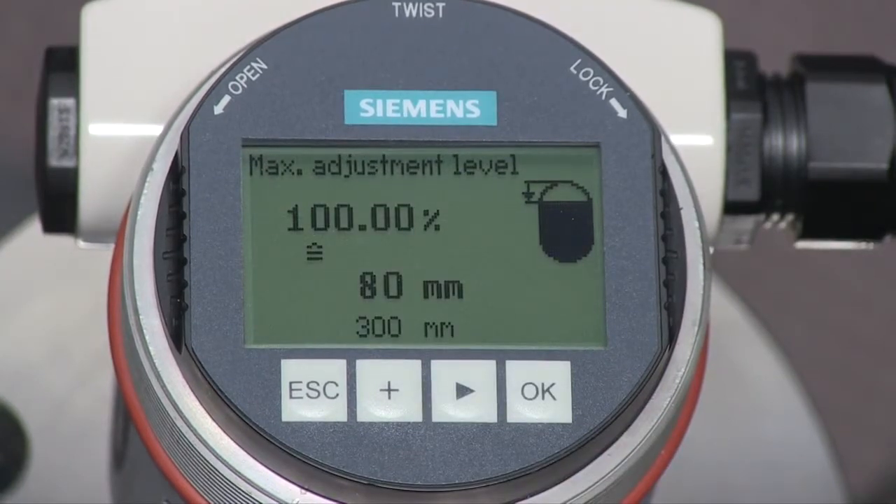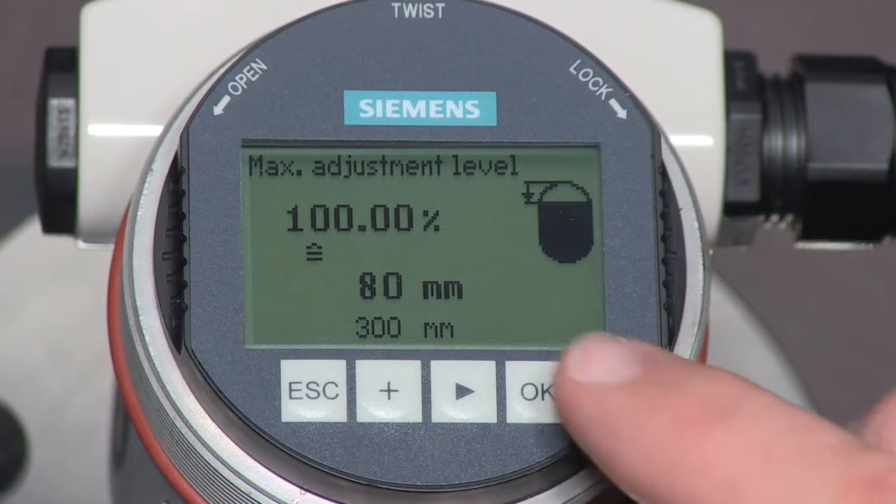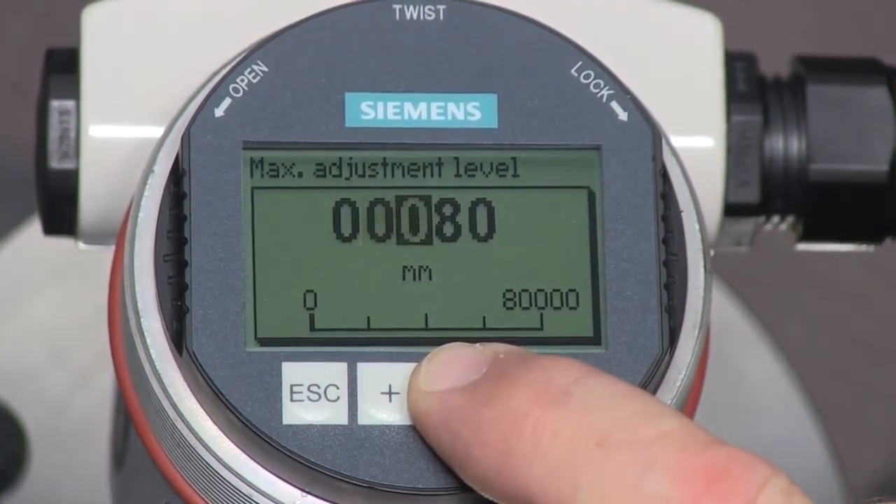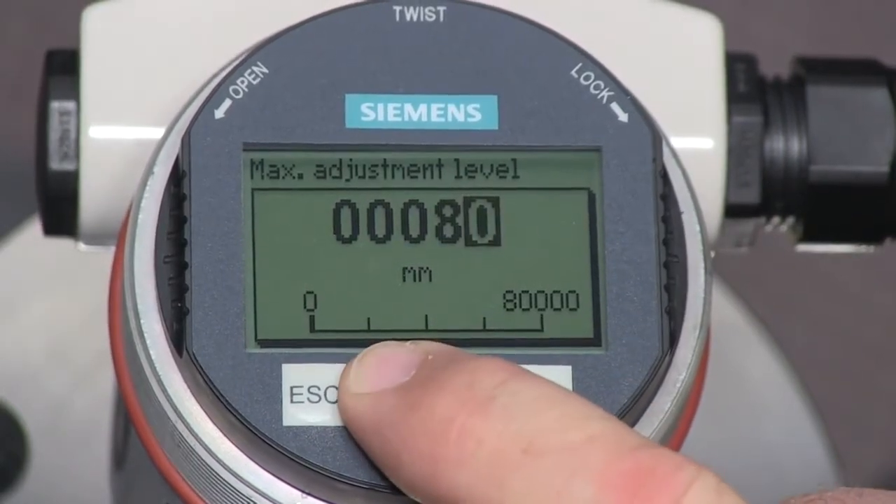The maximum level is measured from the process connection to the maximum liquid level under normal operating conditions. The LR250 requires a dead band of 80mm for water applications. In our application, we will adjust the maximum level to be 85mm. Press the OK key and use the arrow key and plus key to change the value.